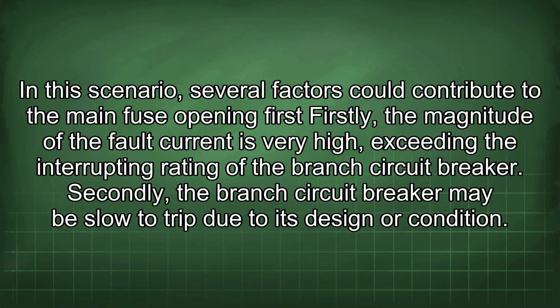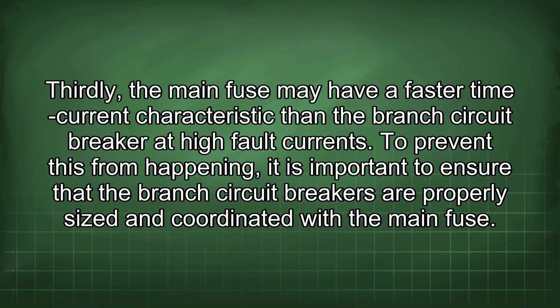In this scenario, several factors could contribute to the main fuse opening. Firstly, the magnitude of the fault current is very high, exceeding the interrupting rating of the branch circuit breaker. Secondly, the branch circuit breaker may be slow to trip due to its design or condition. Thirdly, the main fuse may have a faster time current characteristic than the branch circuit breaker at high fault currents.